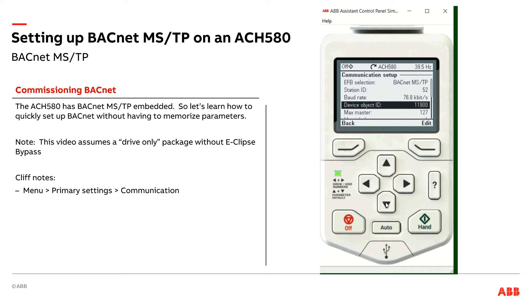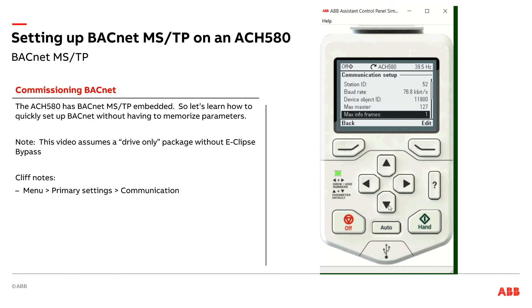If you really want to optimize your wire, you can do things like lower your Max Masters. So if there were only 59 masters on that wire, you could lower that so it's not hunting, polling, and checking for MAC IDs above that. Other settings like Max Info Frames are usually ones you won't get involved in changing too often.